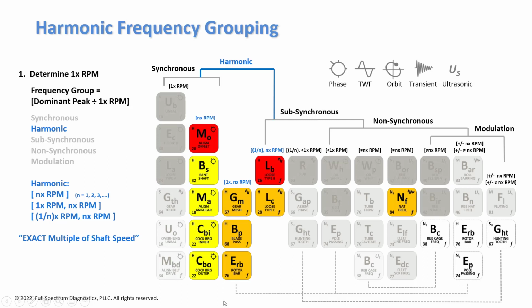Okay, so everything else goes away except for my harmonic column and my natural frequency. My natural frequency is there because it can appear anywhere in the spectrum. It's related to mass and stiffness, not particularly to shaft speed. Okay. So we have a series of faults.